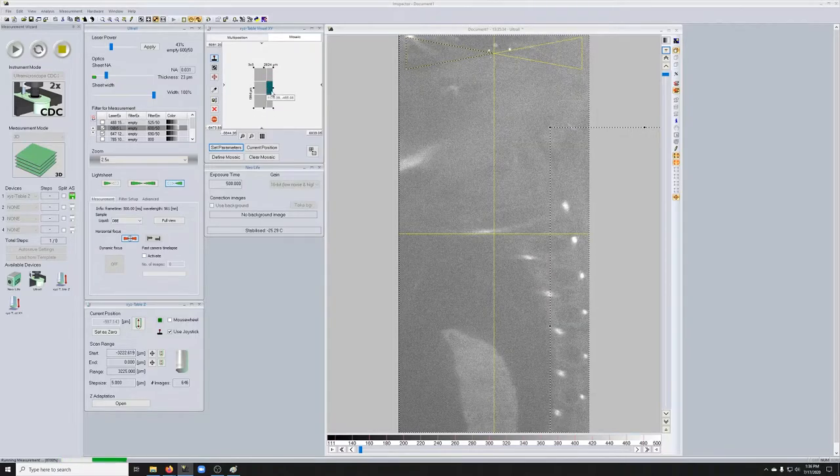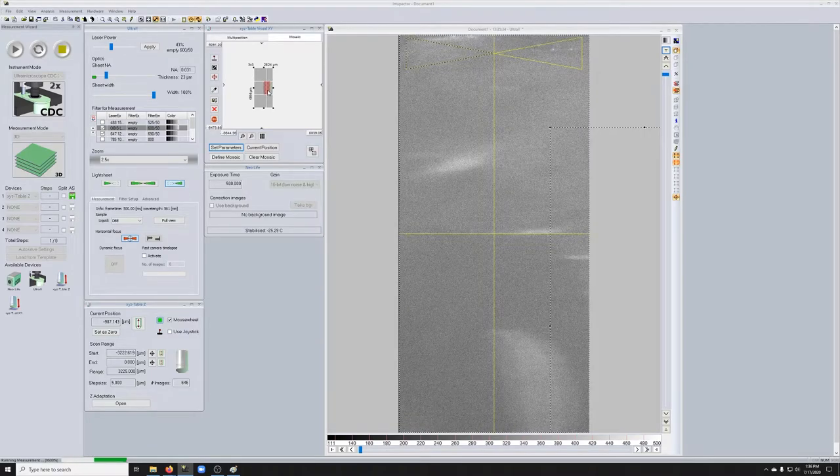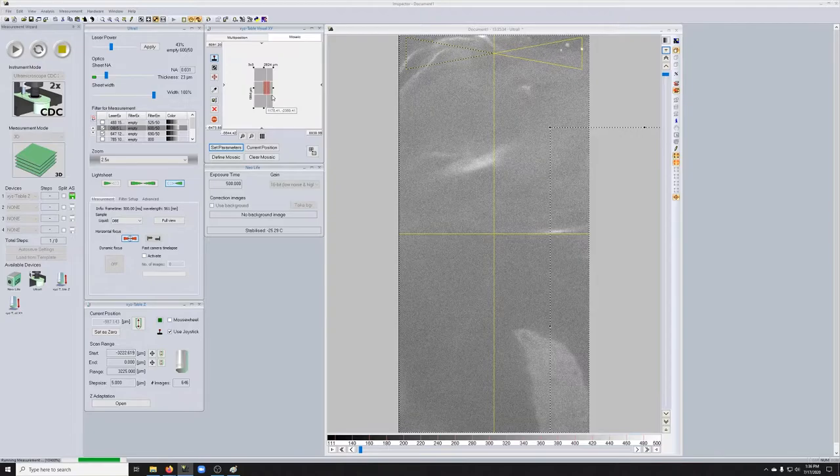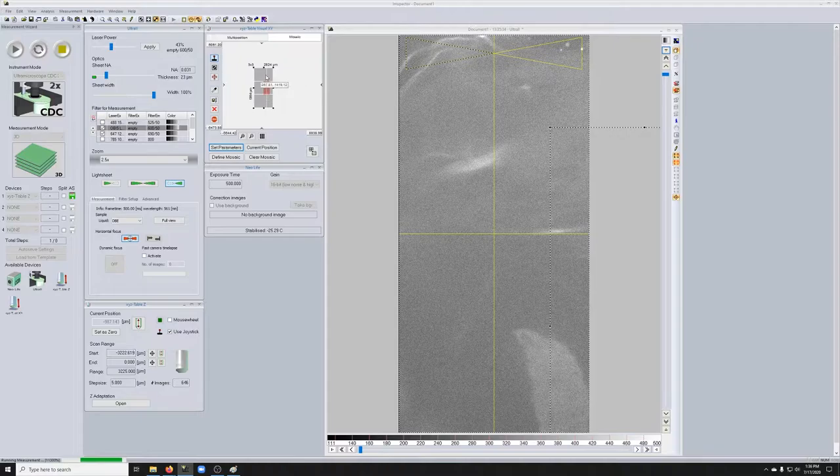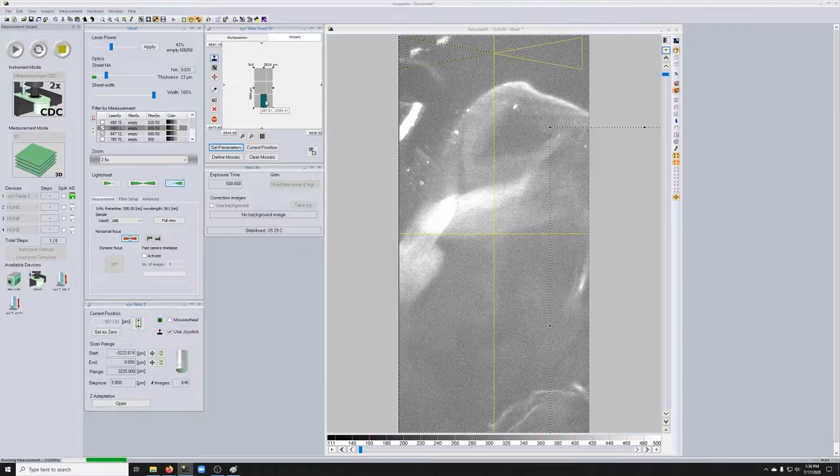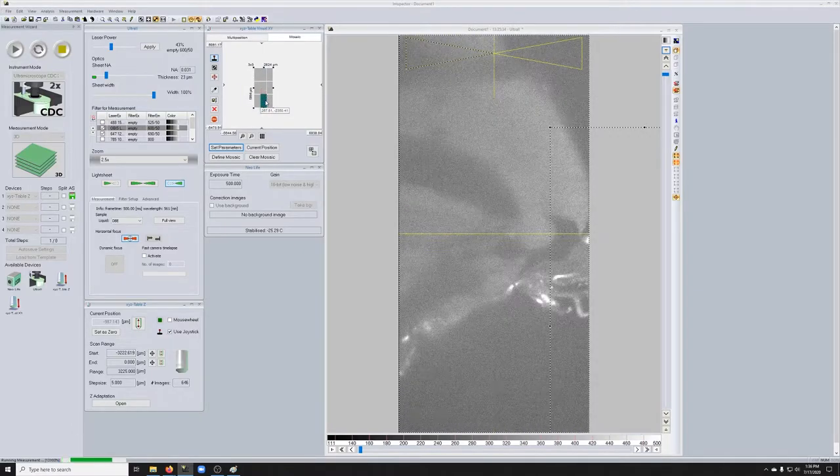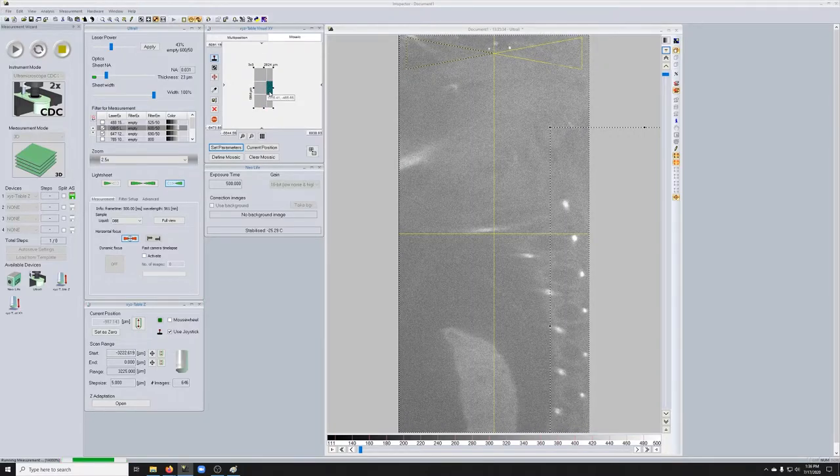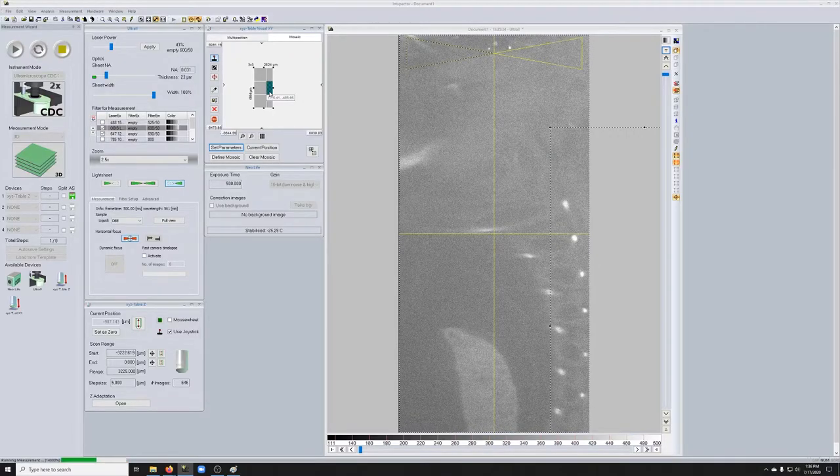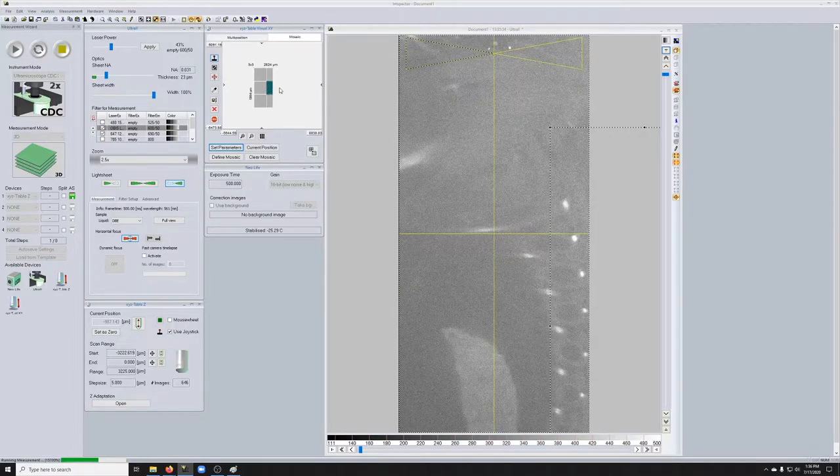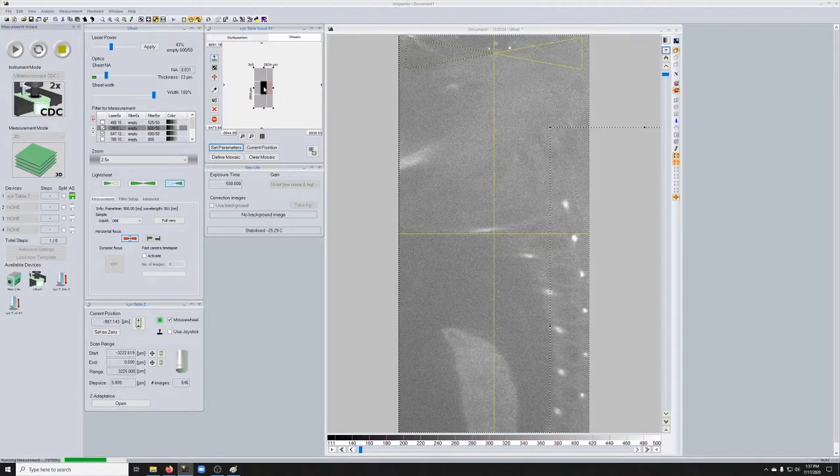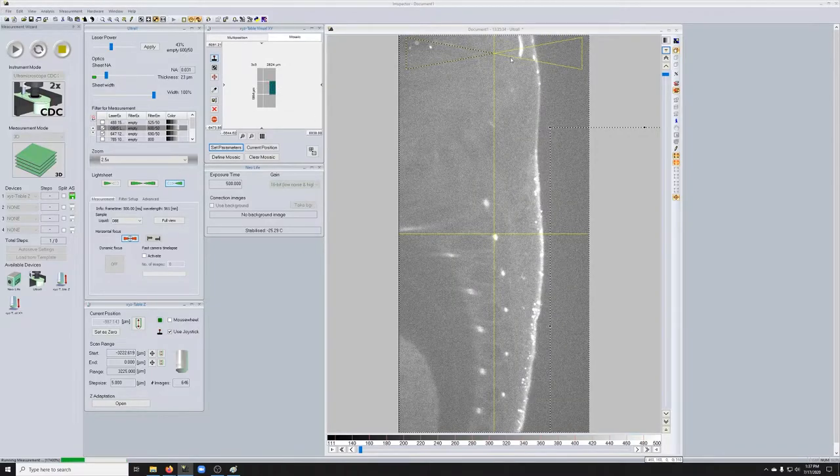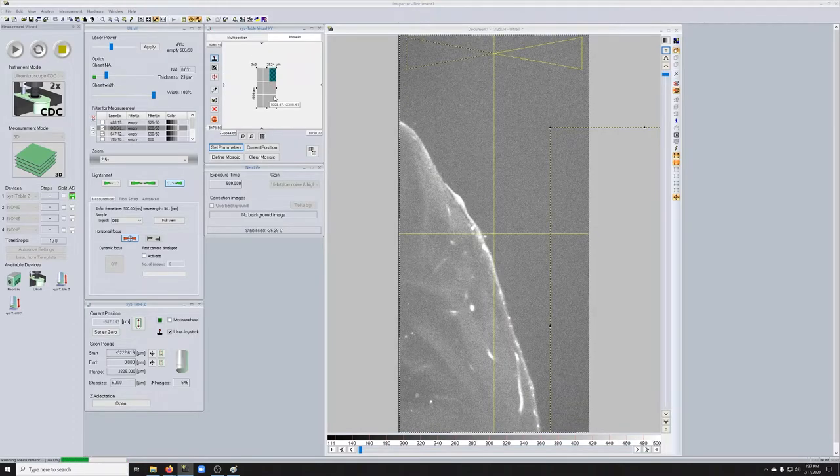And I don't recommend you do this, but be aware that you can grab the red square and move it around. The reason I say don't do this is because it's very easy to make a mistake that sends the stage shooting off into a weird position. So you will use this to make sure that you're taking an image across the range that you want. And so you should be in a plane where the sample is at its maximal extent so that you can see where to set these limits. So for example, here, one thing I'm seeing is I'm not including the edge. So what I can do is shift this over a little bit so that now I have the edge as part of what I want to image.